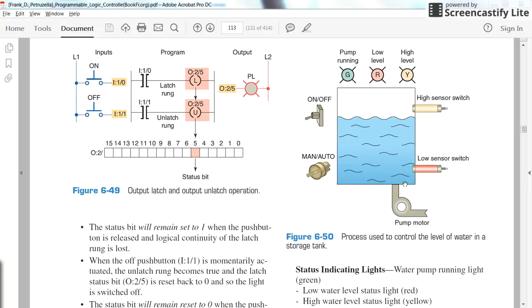Whenever the pump is turned on, the liquid will go out of the tank; whenever it's switched off, the liquid inside the tank will not go out. We have two switches for detecting the level of the liquid inside the tank. We have one low sensor switch — whenever the water level is above it, the switch is closed and gives a high signal; whenever it goes below, the sensor opens. The same applies to the high sensor switch.